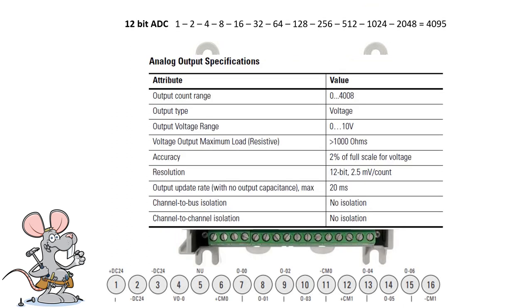For the analog output, the attribute output count range shows 0 to 4008 — I couldn't find an explanation for that in the manual. I'm thinking it's 4095, just like the inputs, since it's 12-bit at 2.5 millivolts per count. That means as you run the analog value up and down, it goes in 2.5 millivolt jumps: 0, then 2.5, then 5 millivolts, 7.5 — nothing in between, because this is converting from digital to analog. There's only the one analog output, at pin 4.